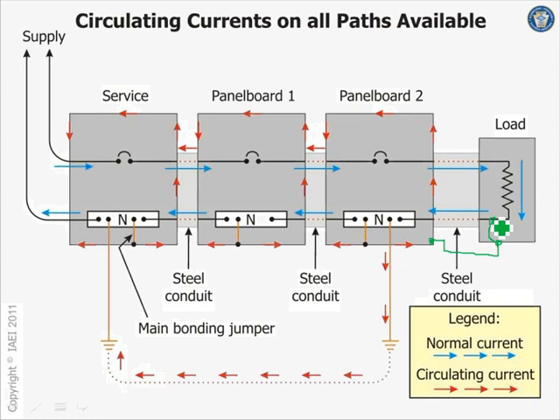When it comes to grounding electronic equipment, when you take this one into the server, you take it even further to different voltages, right? I don't know, 24 volt or whatever, you take it inside to convert it. Now the equipment on this side is also referenced to the ground, the chassis ground they call it. So I can see that could be a circulating current. So what you do is you isolate the system then.